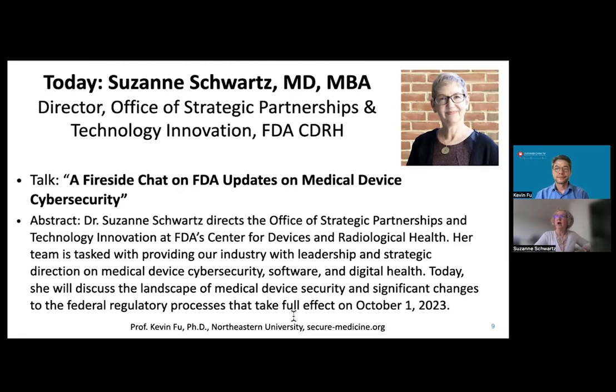Yeah. So I definitely want to point us back to the post-market guidance, which is in effect, which does describe the difference between controlled vulnerabilities and uncontrolled vulnerabilities. Uncontrolled vulnerabilities were the ones that, per the assessment done by a manufacturer, have an unacceptable risk to health. And what we really underscored in that guidance is the importance of addressing those as expediently as possible.